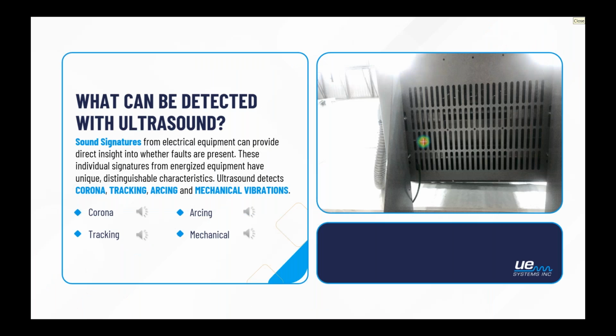So now that we've covered all this, what we're inspecting, how we're inspecting it, good things and bad things to avoid, what we're actually looking for. I mentioned it earlier, but the specific forms of partial discharge that we are looking for are corona, tracking, arcing, and also mechanical looseness. I have a further breakdown of this later, but these are very specific events that we're looking for, and they all have very specific signatures, both in sound and also when we're breaking down the files through spectral analysis.